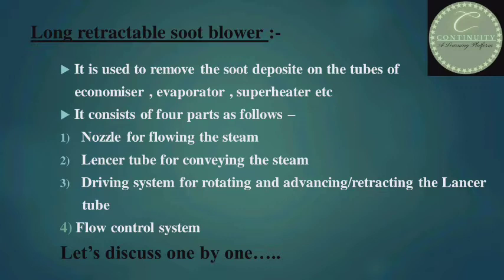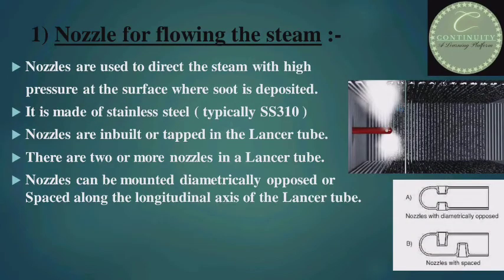Second, lancer tube for conveying the steam. Third, driving system for rotating and advancing or retracting the lancer tube. And fourth, flow control system. Let's discuss one by one. Nozzles are used to direct the steam with high pressure at the surface where soot is deposited. It is made of stainless steel, typically SS310. Nozzles are inbuilt or tapped in the lancer tube; there are two or more nozzles in a lancer tube. Nozzles can be mounted diametrically opposed or spaced along the longitudinal axis of the lancer tube. In the figure, A shows nozzles with diametrically opposed arrangement and B shows nozzles with spaced arrangement.